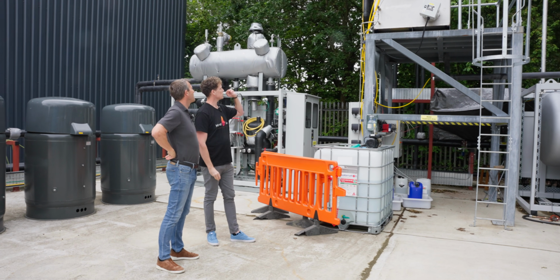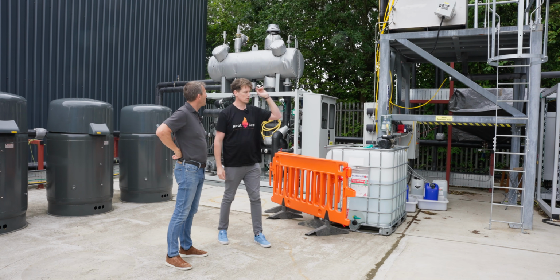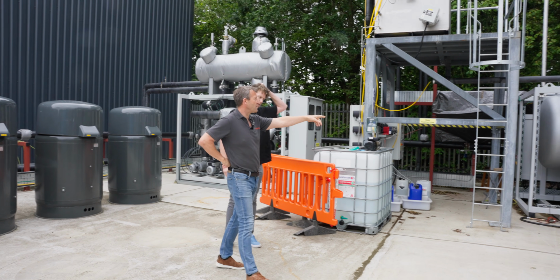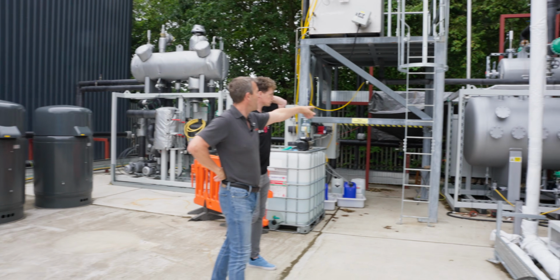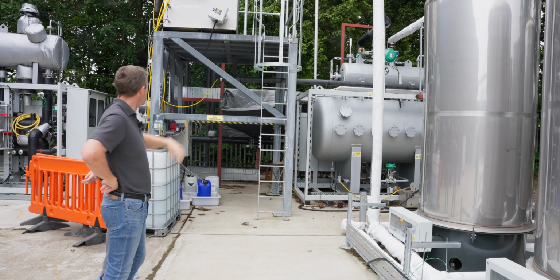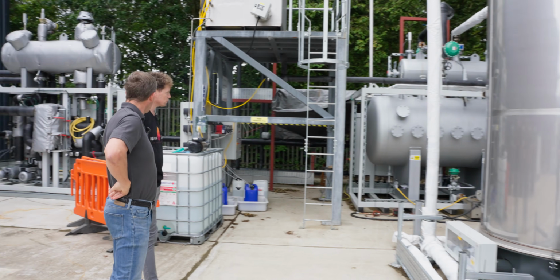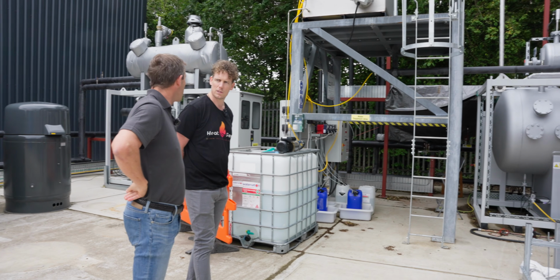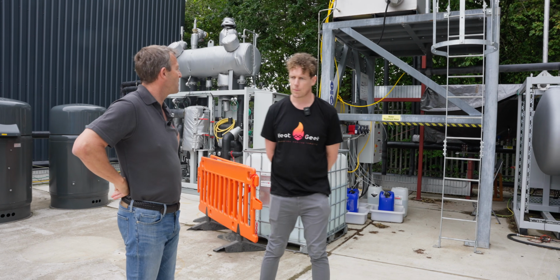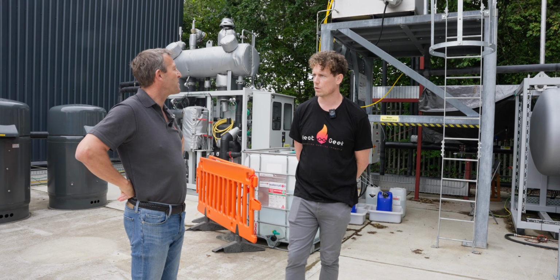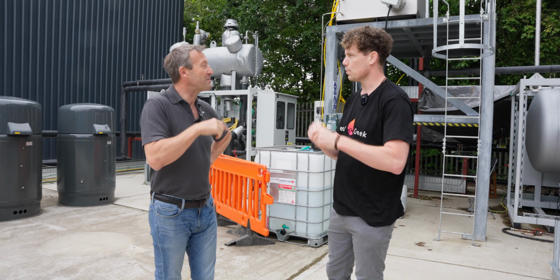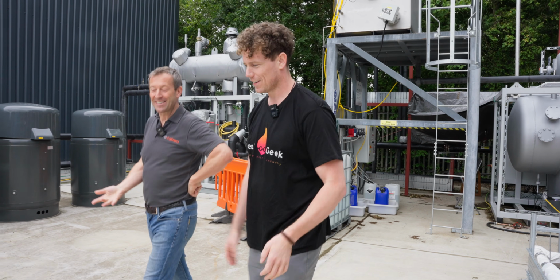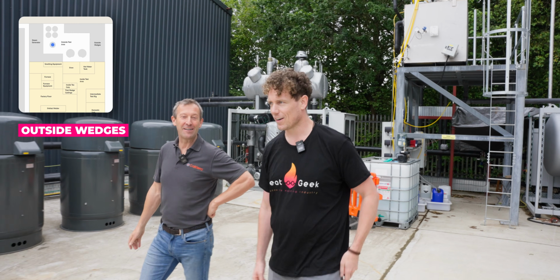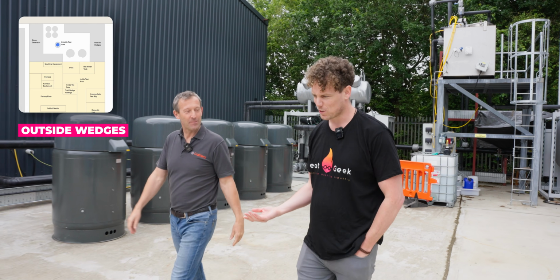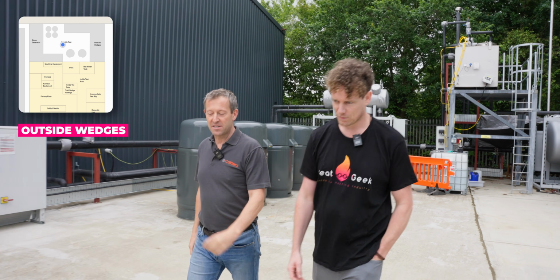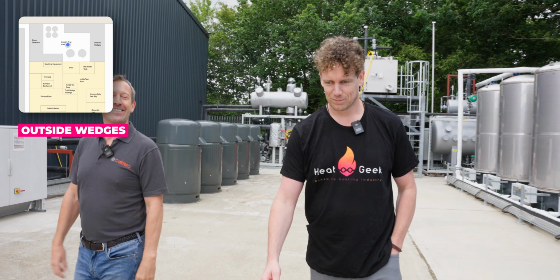The water storage for that is only about 20 litres, whereas inside the tank we'll have a few tons. That water is basically almost never replaced - it shouldn't be. It's filled with some kind of deionising process on site, but it doesn't matter much once it's been distilled so many times - it's cleaned immediately, which is why we just want the same water going around and around, so there's nothing building up in there. So actually you could probably fill it with tap water, though that's not best practice.